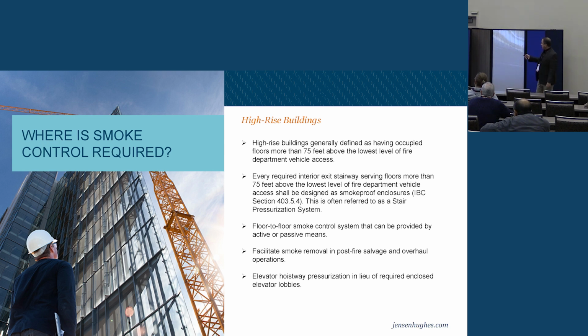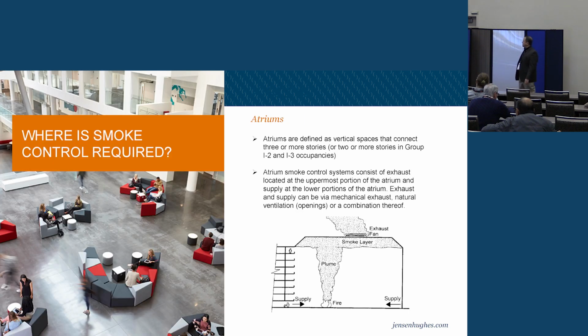Then there's smoke removal for post-fire, which is probably the most prevalent now in most jurisdictions. When the fire department gets there, how can they get rid of the smoke and do salvage and overhaul? And then elevator hoistways. There are 2 options in the fire protection architectural world. You can either enclose the lobbies of your elevators and not provide pressurization, or you can pressurize the elevator shaft. We'll talk about why that's important and what it does in a minute.